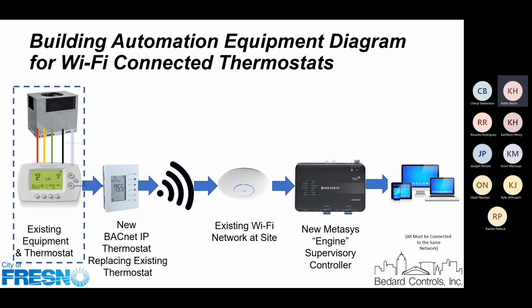Right now, the facilities people are the people who are able to log in, but that can be expanded as necessary. The idea is we don't have to change this wiring here. I hesitate a moment because in a lot of cases, you'll notice there's 5 wires that we need to communicate. A lot of times there's only 4 wires, especially in some of the older buildings. So we have to use what we call an add wire that kind of pretends to be a 5th wire so that we have constant power to the new thermostat because it's broadcasting on a regular basis back through the Wi-Fi network.